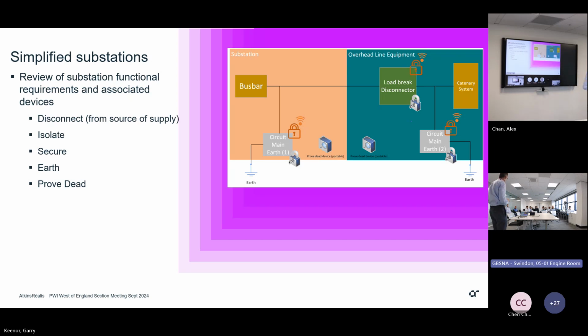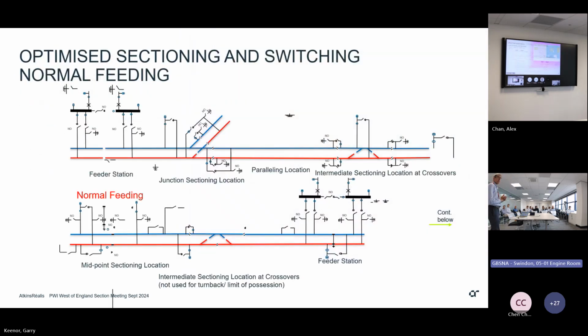That was just a very simple block diagram that we then took to develop how we can simplify the substations. We actually found that we can get rid of nearly all the substations - we can deliver those functions with load break isolators. Combined with modern SCADA systems and IEC 61850 substation technology, we can link all our isolators up, fast acting.